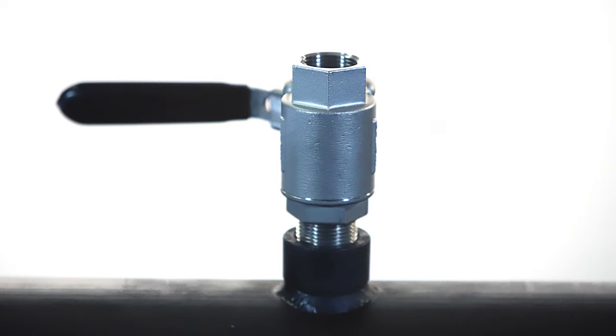To ensure correct installation, the access hole into the pipe must be at least one inch in diameter minimum and the isolation valve stack height must be 7 inches or less. This measurement must be taken from the top of the pipe without insulation to the top of the isolation valve.